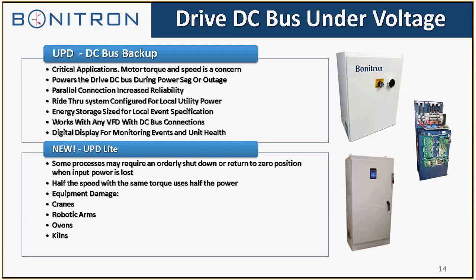So even though the drive may ride through, the process may still shut down because of a change in speed or torque of the motor. In some applications, such as extrusions, there has to be a steady motor speed to have a good, consistent extrusion. The drive may continue running, the motor may continue running, but due to a utility power event it may slow the motor down, and that can cause you to run scrap product without even knowing about it if you're not paying attention. So a whole afternoon of production can be wasted.